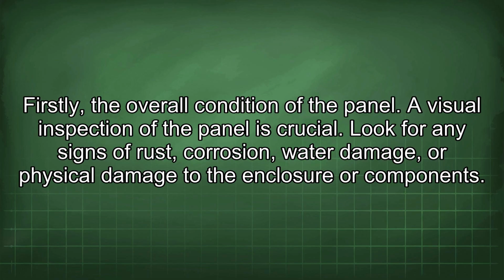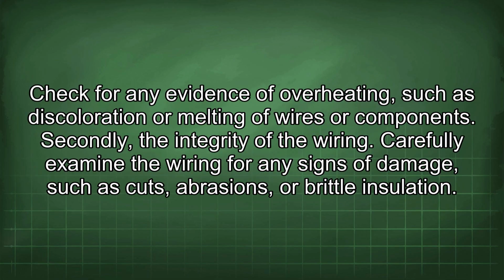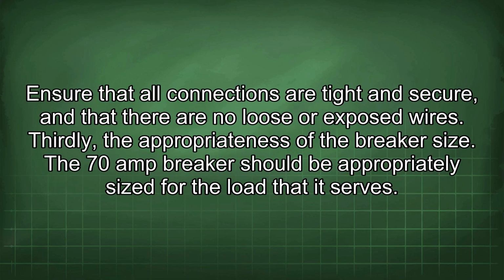Look for any signs of rust, corrosion, water damage, or physical damage to the enclosure or components. Check for any evidence of overheating, such as discoloration or melting of wires or components. Secondly, the integrity of the wiring. Carefully examine the wiring for any signs of damage, such as cuts, abrasions, or brittle insulation. Ensure that all connections are tight and secure, and that there are no loose or exposed wires.